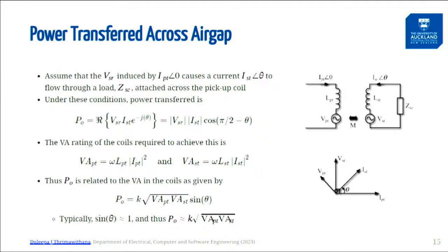So if you want more power, you put more volt-amps into the two coils or improve the coupling between them. For a typical inductive power transfer system, coupling is around 10 to 20%, maybe 30% if you're lucky. 40% would be quite a luxury, I'd say.